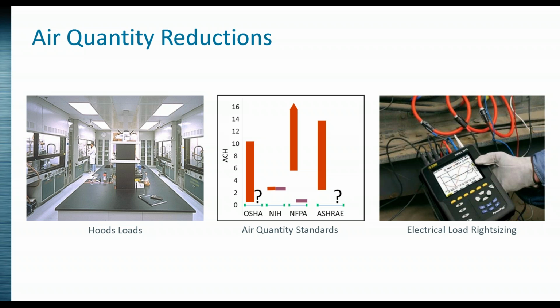There are air quantity standards, so thinking about minimum ventilation rates. 10, 15 years ago, many projects were still at 10 to 12 to 14 air changes per hour minimum, consuming immense amounts of energy, diluting all those spaces. We've seen a big shift where, from an occupied perspective, more owners are operating at 6 and 4 air changes per hour, and considering unoccupied set points that are even lower.